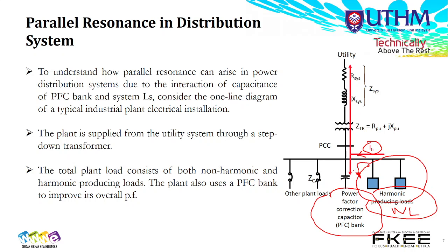So this harmonic goes through to the capacitor. Try to imagine this harmonic flowing to the capacitor in parallel with the impedance of the transformer and generator. From the harmonic point of view, this goes to the ground, and we have a ground connection, so it's parallel with this one. That's why we call it a parallel resonance.